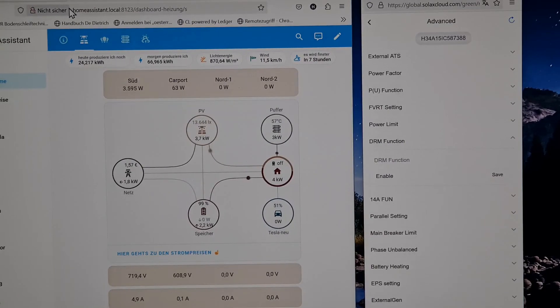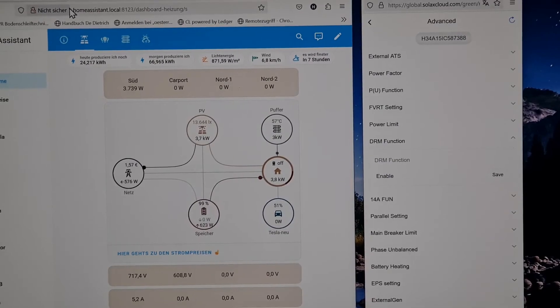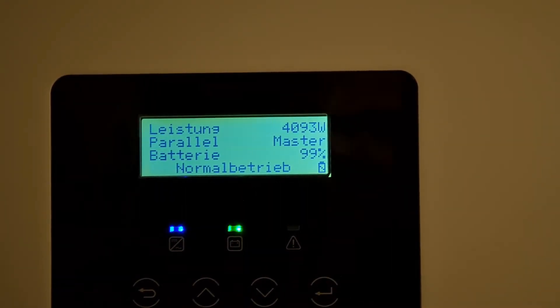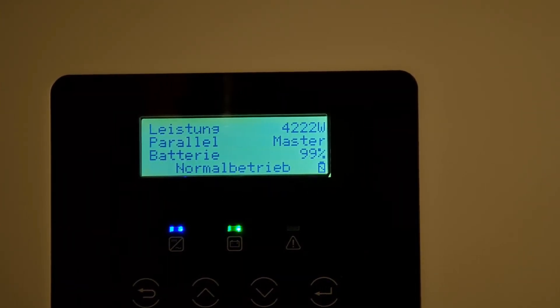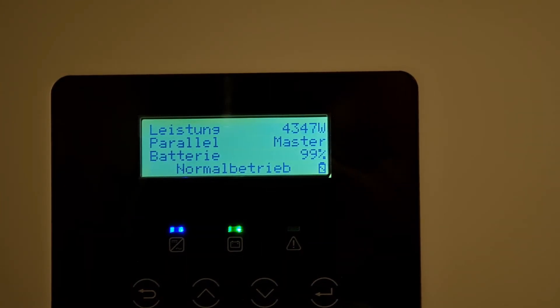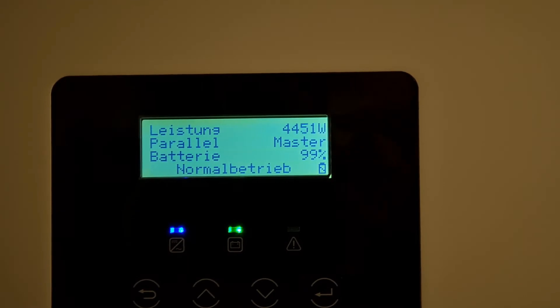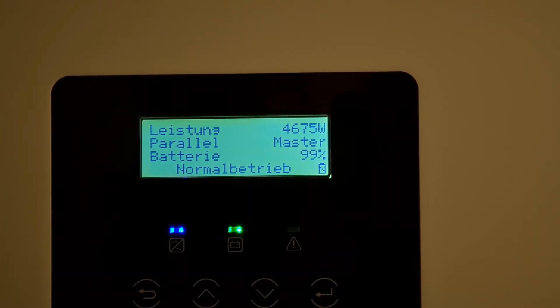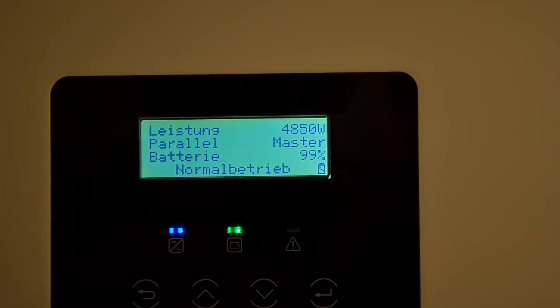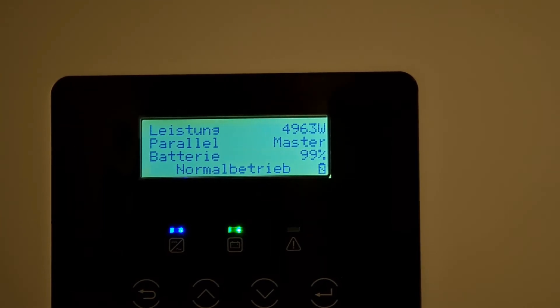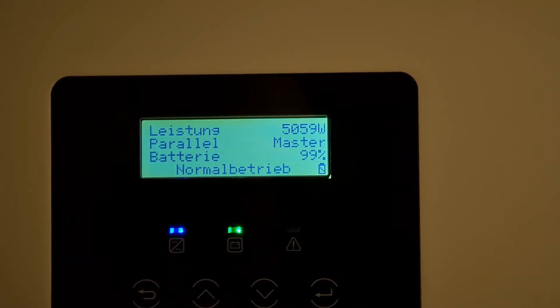DRM-1 is also possible — DRM-1 means the inverter does not allow drawing power from the grid. Now I'll show you that operating mode DRM-5 can also be controlled remotely. We'll switch back to the inverter display. We're now at 4 kilowatts, so we're going to control it remotely now. This is what the grid operator actually wants to do, since we're currently in normal operation. Now we're going to set a pin — the grid operator provides a potential-free contact, which they can open or close using a relay. I connect this potential-free contact to the two correct pins on the DRM board. We're now going to activate DRM-5 by setting the pin to the correct position — this simulates what happens when you close the relay.